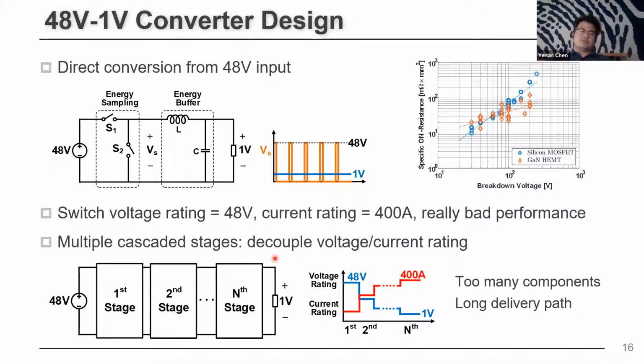Another solution is we cascade multiple stages to decouple the voltage and current rating. For example, the first stage converts 48 volt to half the input voltage, 24 volt. The voltage rating of the first stage is still 48 volt, but the current rating is only twice the input current. For the second stage, we do a conversion with a lower voltage conversion ratio, for example from 24 volt to 12 volt, so the conversion ratio is half. For the following stages, we do similar conversions. In this way, the voltage rating and current rating can be decoupled, and the switch does not need to block the high voltage and carry the high current at the same time.